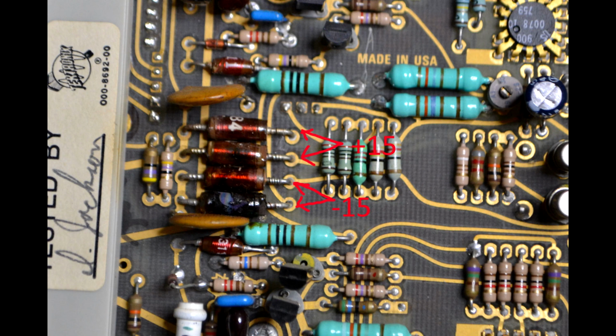The problem may be indicated by overheated decoupling resistors or inductors. As can be seen here, two of the inductors are clearly overheated. Some mainframes have linear power supplies which will go into current limit mode. The current in this mode is high enough to overheat the decoupling parts. Other mainframes have high-efficiency switching supplies which go into a benign tick mode. This will usually not cause overheating of the decoupling parts.